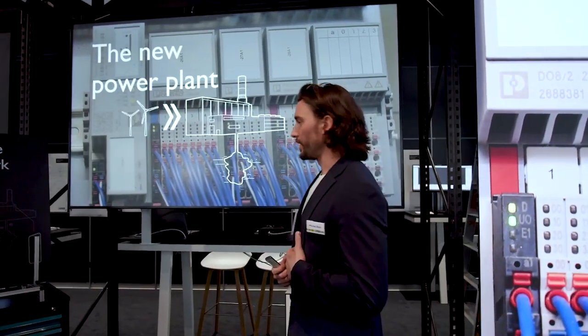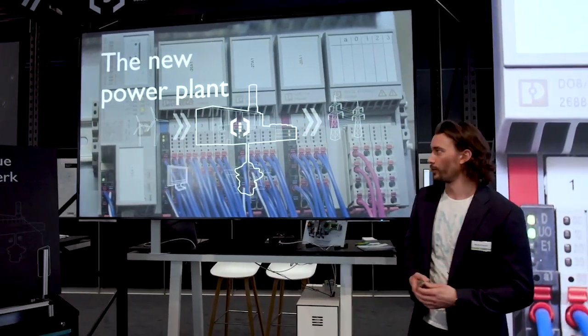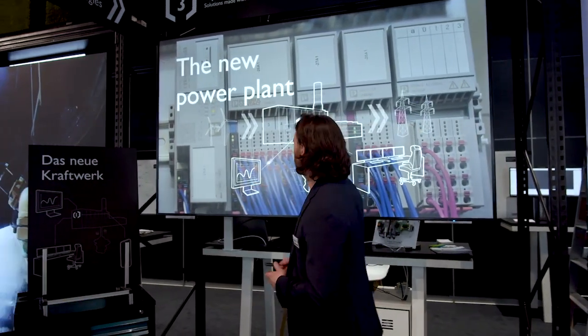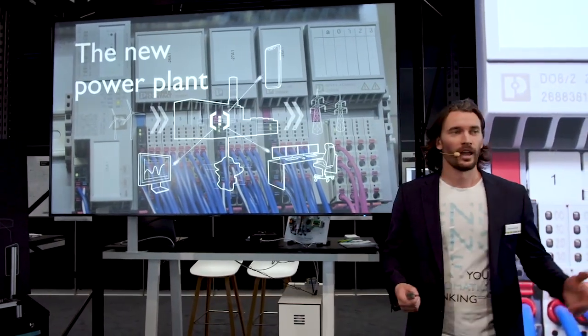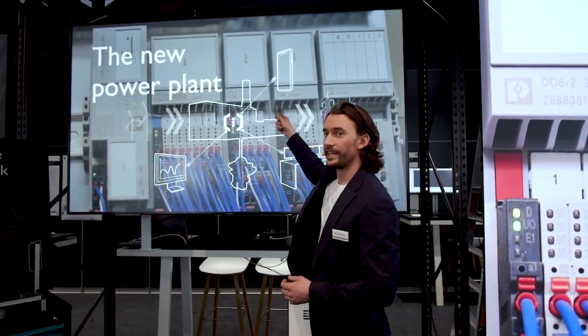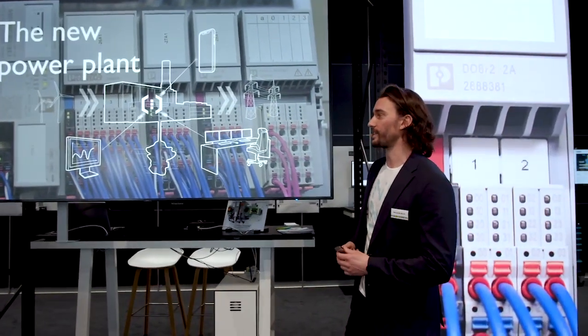Our new PLCnext control reads the process data from the existing older power plant controller and forwards this to local visualization devices. We achieve this using the OPC UA communication standard. Simultaneously, this data is also forwarded to the control center at a remote facility in Wilhelmshaven, and the technicians from the power plant can see the process data and monitor the status of the power plant using their mobile devices.